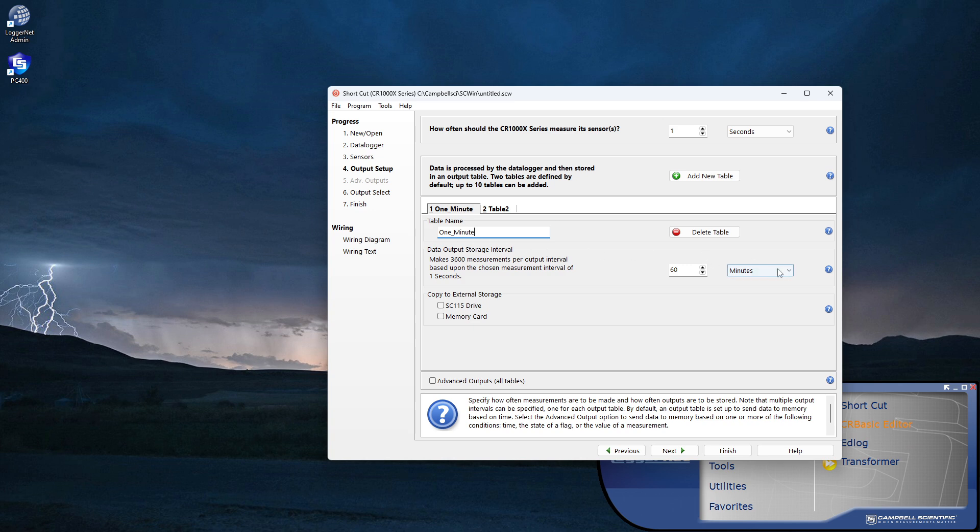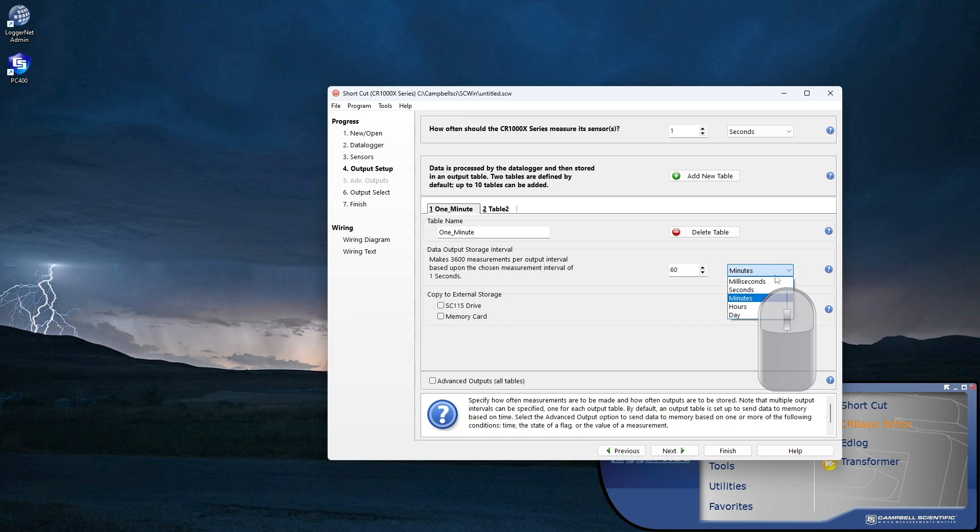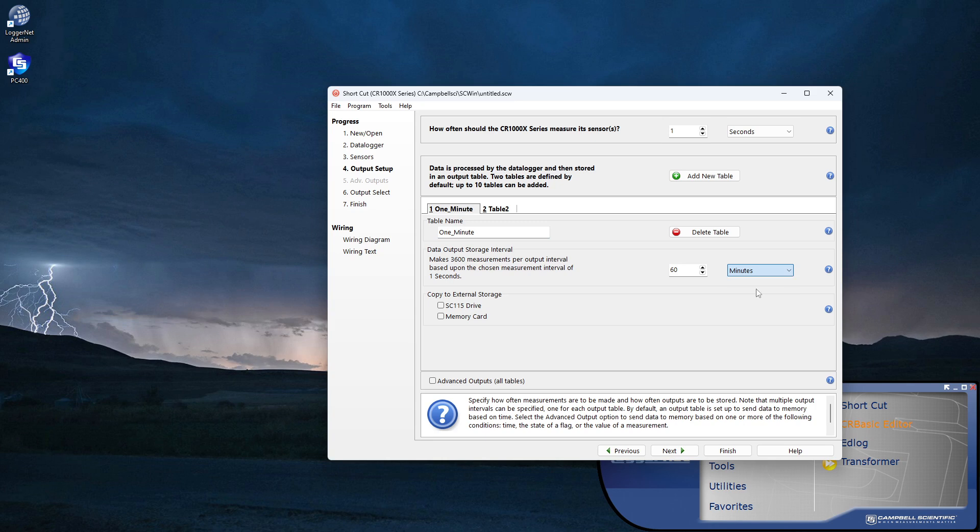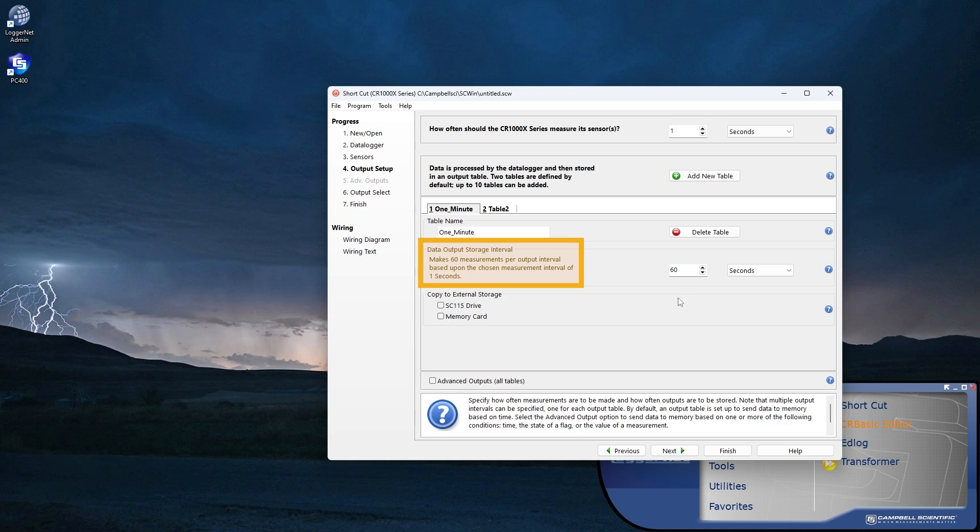Now, set the data output storage interval. In this example, I want to store data every 1 minute, or 60 seconds. Since the default is 60, choose seconds as the units. I could also have changed the interval to 1 and used minutes. Notice that when I change the interval, this text changes to reflect the number of measurements that will be included in the storage interval.